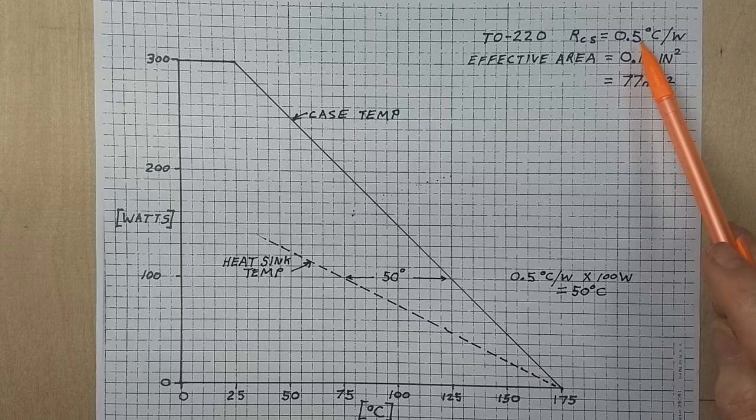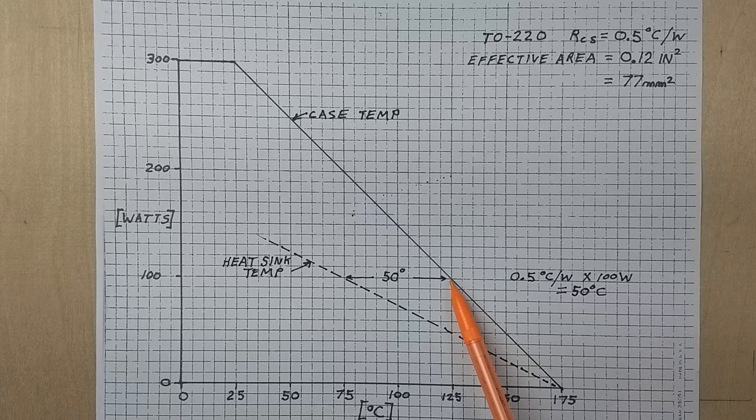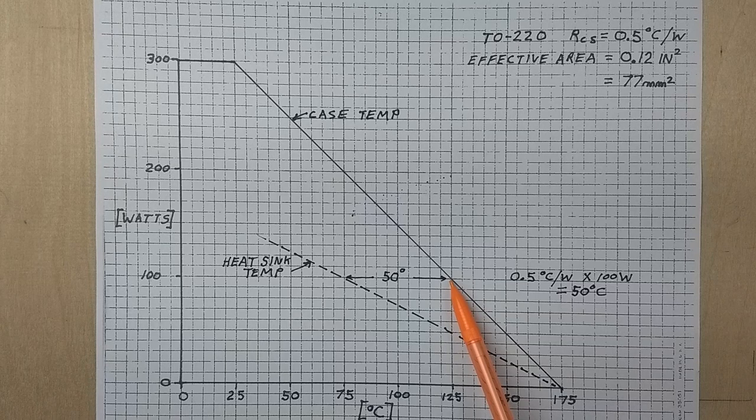Now with a thermal resistance from the case to the sink of 0.5 degrees C per watt, when we're dissipating 100 watts, a heat sink has to be 50 degrees cooler than the allowable case temperature. So that's a very important factor.